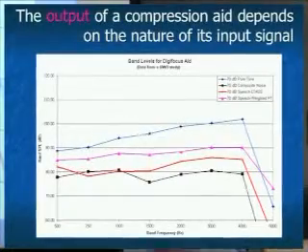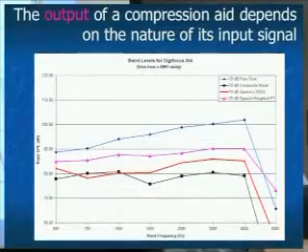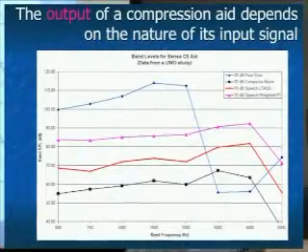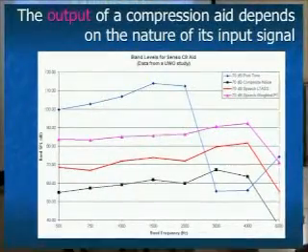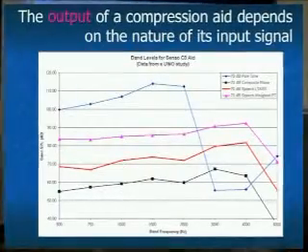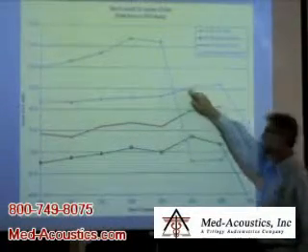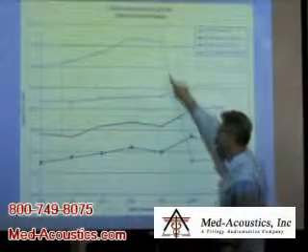What's really correct is speech, since that's what we're trying to make audible, intelligible, and comfortable. We don't care about pure tones - they could be attenuated like noise by the hearing aid. Here's a different hearing aid circuit treating all four signals quite differently. With a pure tone, this particular digital hearing aid's output dropped to almost nothing above 2000 Hz because the circuit thought the hearing aid was going into feedback and cut the output way down due to its feedback suppression algorithm.